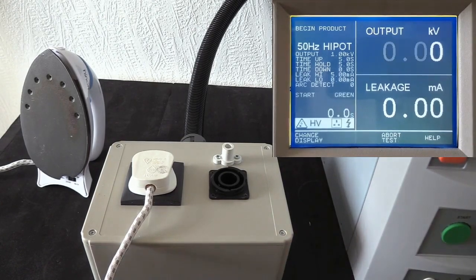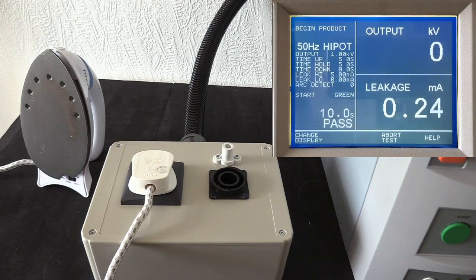You'll notice now the voltage is rising. We're getting some leakage, but nothing high. The test is now in its hold phase, and at the end of the test, the leakage is less than the 5 milliamps, and therefore we receive a pass.